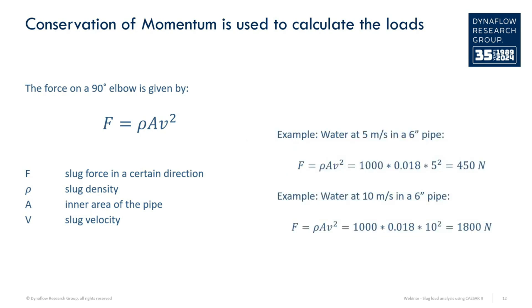So what sort of forces can be expected from a slug traveling through a piping system? As an example, a slug formed by water traveling at 5 meters per second in a 6 inch pipe gives a force of about 450 Newtons, while at 10 meters per second it increases to almost 2 kilonewtons.